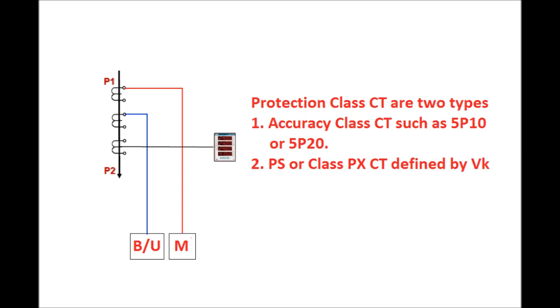Protection class CTs are generally two types: one is the Class P CT and another is the PS or PX class CT. Class P CT is defined by the accuracy limit factor. For example, 5P10 — where 5 defines the accuracy and 10 is the accuracy limit of the CT. That is, if 10 times the rated current flows in the primary side of the CT, then there will be a maximum error of 5% in case of a 5P10 CT.